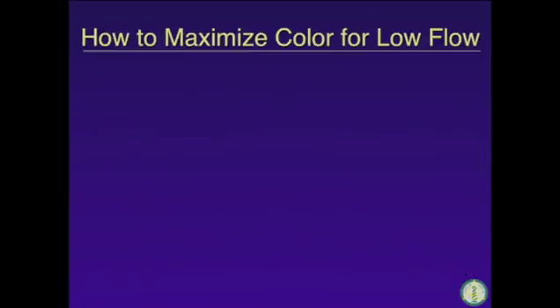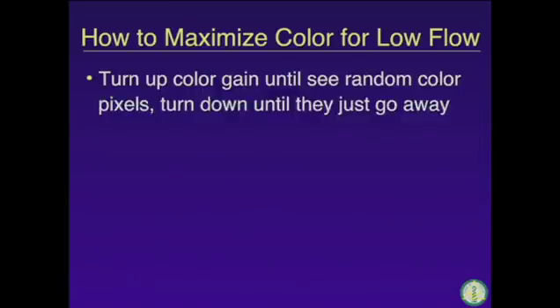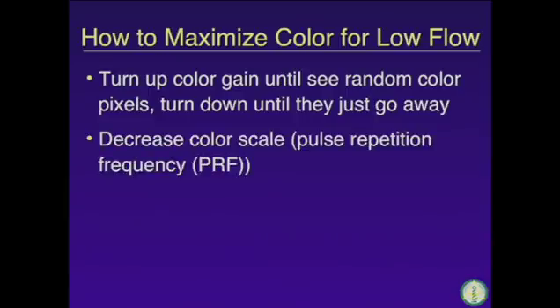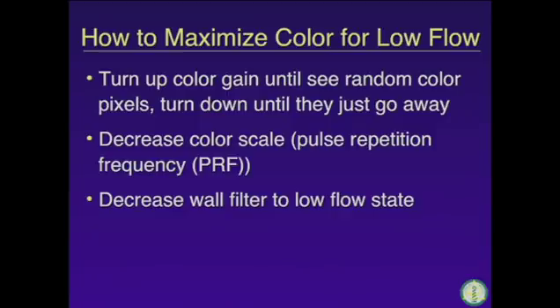post-stenosis. All right. Next topic is how to maximize color for low flow. There are a lot of pitfalls in color Doppler imaging, and this is one of the biggest ones that you can fall into. Again, you need to address your color gain setting, turn the color gain up until you can just see random color pixels, and then turn it down until they just go away. You need to decrease the color scale, the PRF, and then decrease the wall filter to a low flow state.